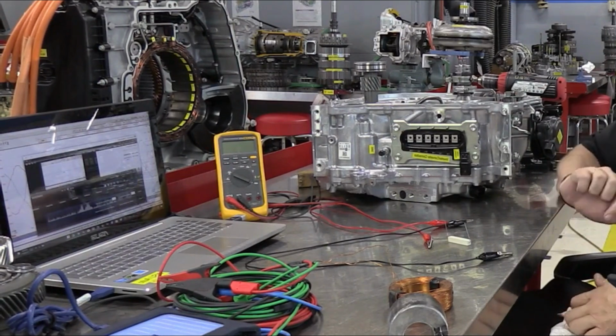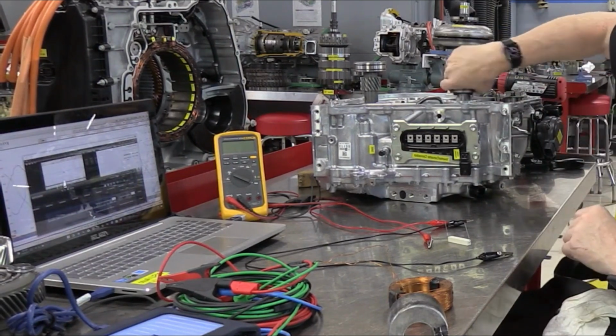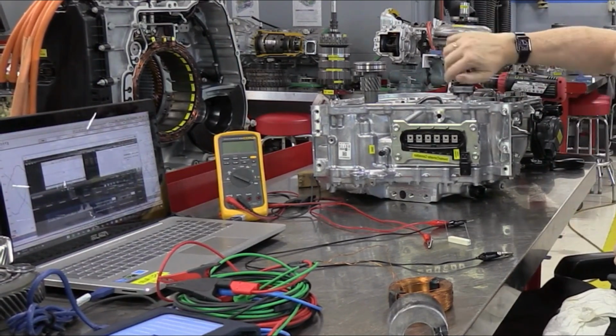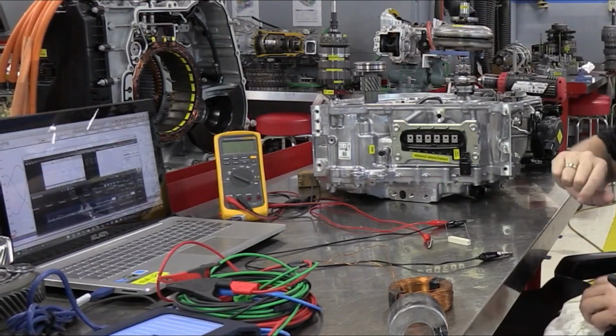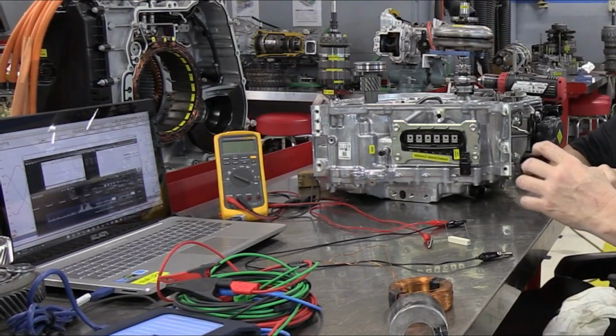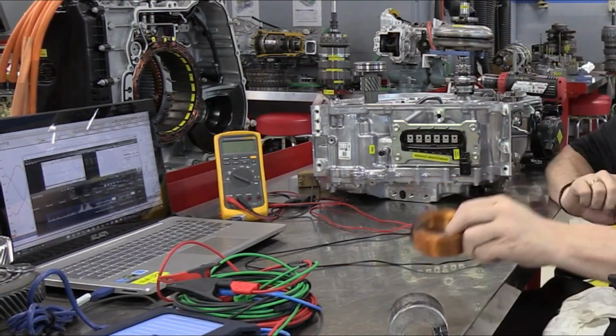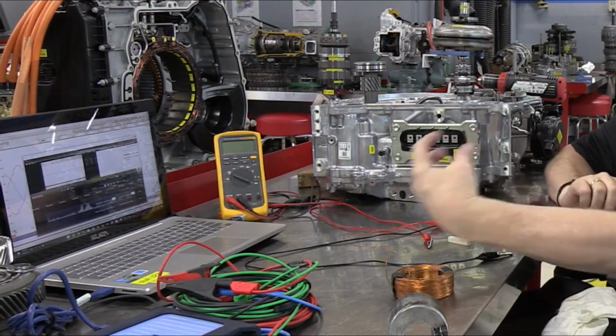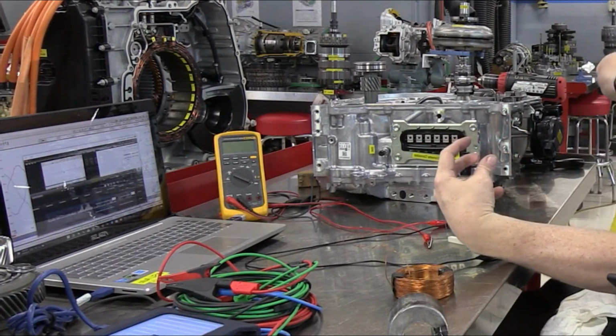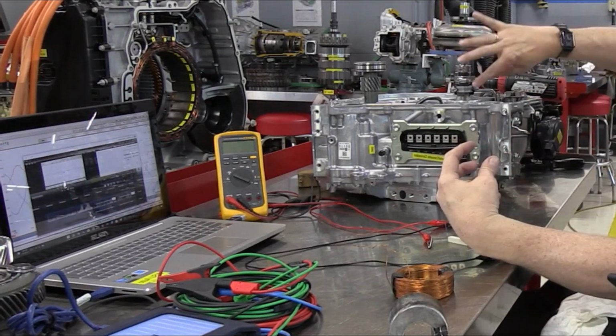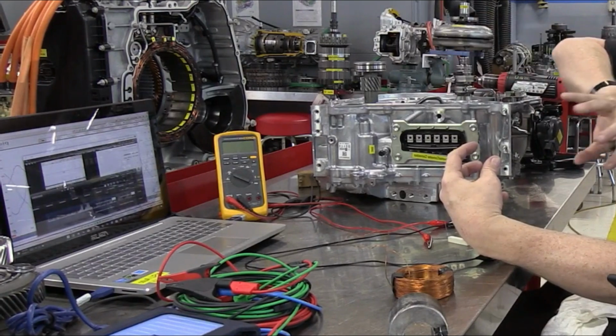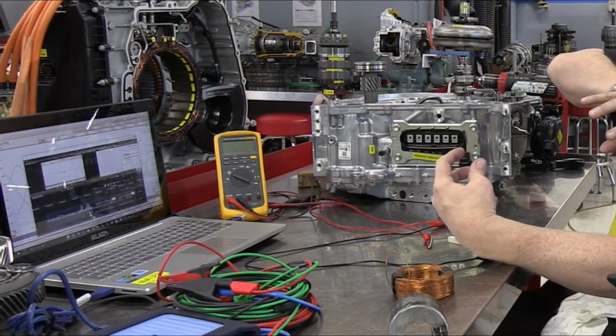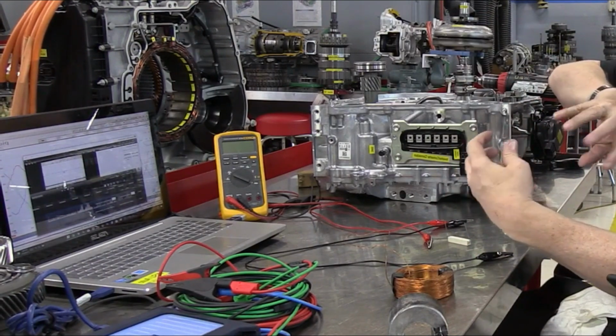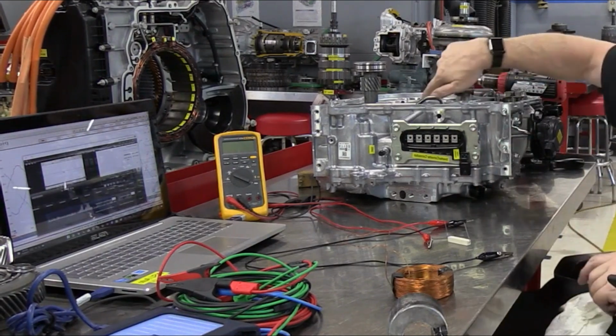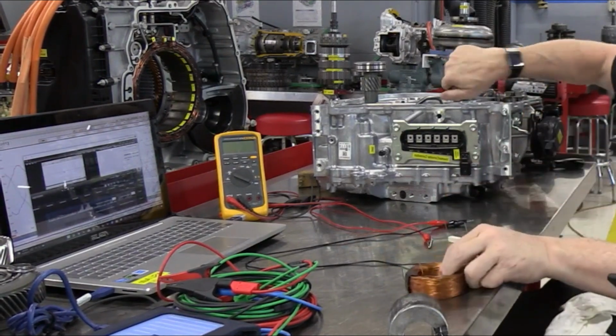Case study number 3. A fleet electric bus began experiencing inconsistent performance and overheating in its induction motor, particularly during heavy acceleration. The issue was traced back to the motor winding. Analysis: the symptoms. The buses were brought in for inspection after multiple drivers reported reduced acceleration and increased noise from the motor compartment.